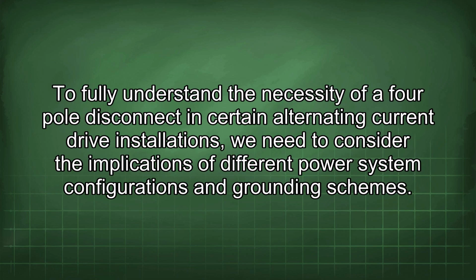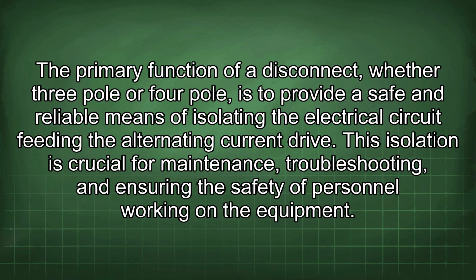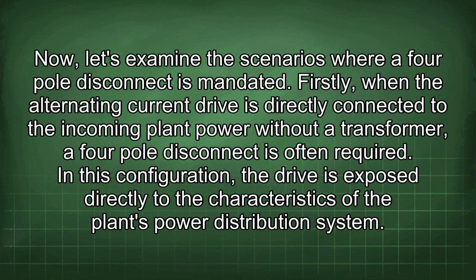To fully understand the necessity of a 4-pole disconnect in certain alternating current drive installations, we need to consider the implications of different power system configurations and grounding schemes. The primary function of a disconnect, whether 3-pole or 4-pole, is to provide a safe and reliable means of isolating the electrical circuit feeding the alternating current drive. This isolation is crucial for maintenance, troubleshooting, and ensuring the safety of personnel working on the equipment. Now, let's examine the scenarios where a 4-pole disconnect is mandated.